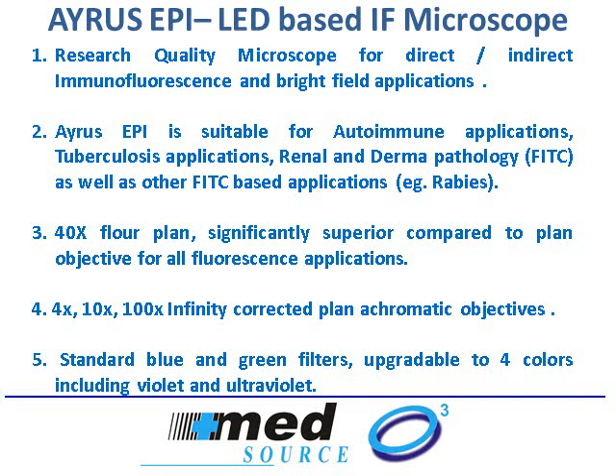One of the huge advantages of this particular microscope is that the 40x objective, which is the main objective for all fluorescence applications, is a fluor plan objective. This is a very expensive and very superior objective compared to the standard plan objectives available on most microscopes. So a 40x fluor plan has a huge advantage because it can read fluorescence better. You can even see low fluorescence quite well. The images are sharper. So this is one big advantage that our microscope brings in compared to competition. The other objectives 4x, 10x and 100x are infinity corrected plan achromatic objectives, the industry standard.